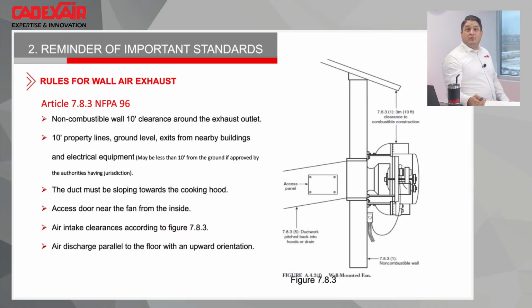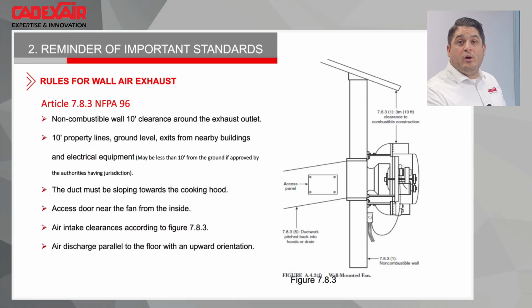Other quick point, it's about what I've been asked almost every week: how to exhaust on the wall as per NFPA 96. First thing first, there are two considerations. When you want to do a kitchen wall exhaust, you need to have 10 feet of clearance of non-combustible material around the exhaust point. So if you have, I don't know, a wooden structure or anything on the outside of the building that is a combustible structure, you're not allowed to exhaust through the wall.